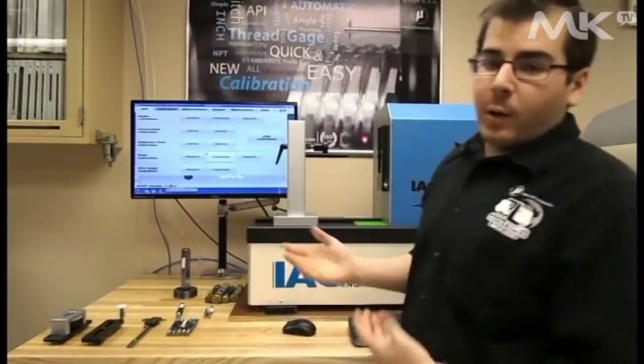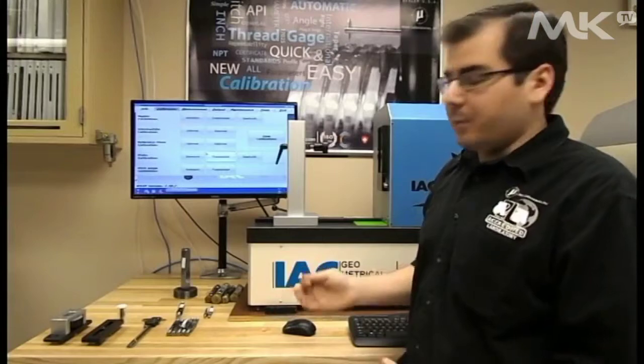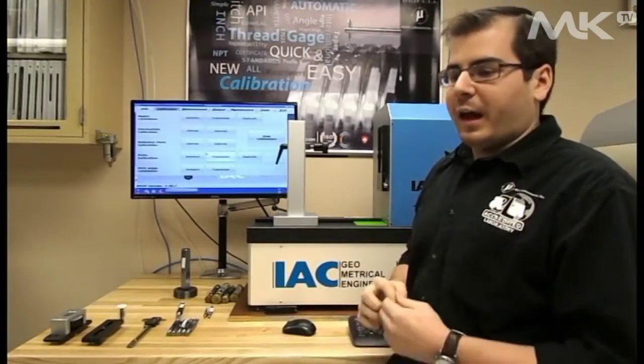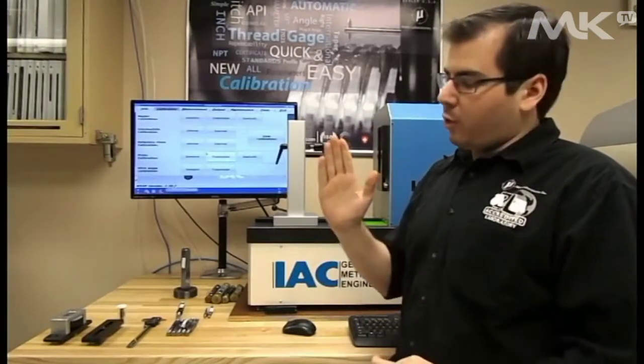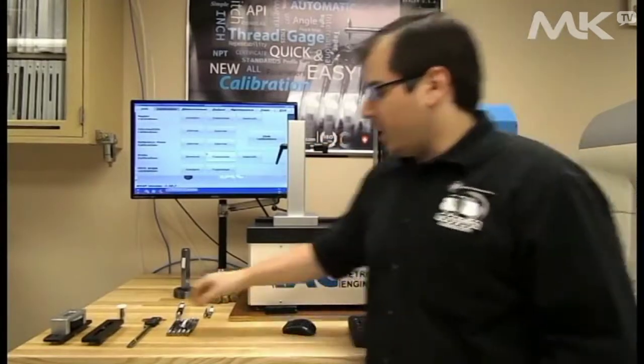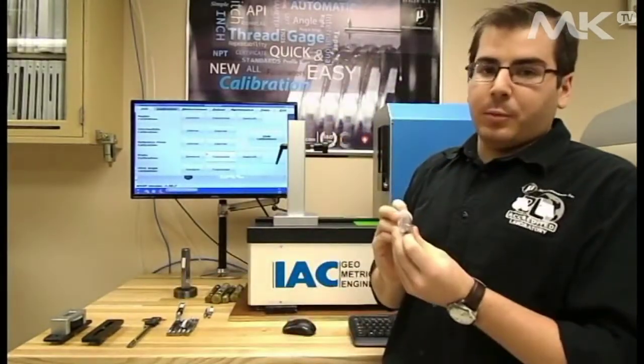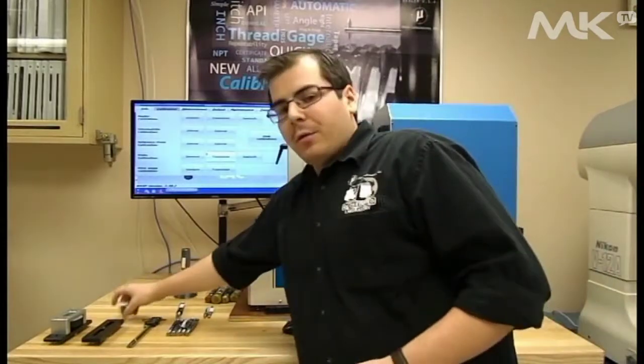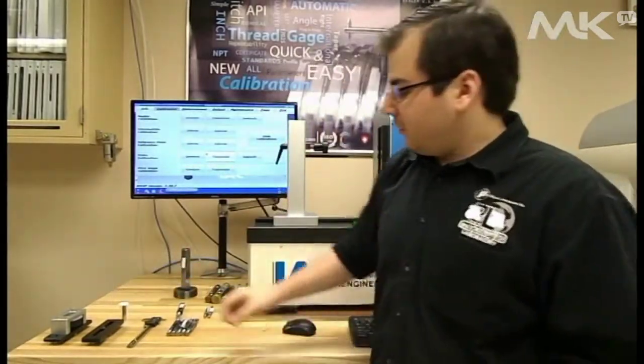Now, it may be confusing why we need a master and an intermediate calibration. An intermediate calibration is actually used to determine if the probe is on center. Using a known diameter of an intermediate piece, it tells how far off center it is and compensates.